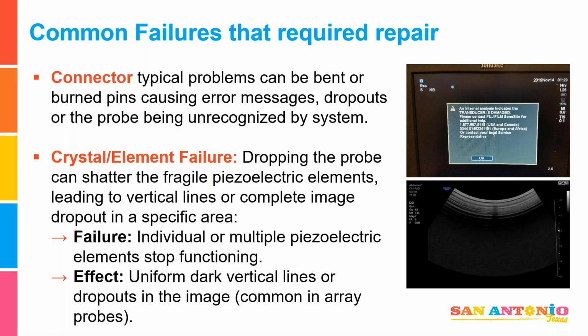In this case, I'd try multiple probes in multiple ports, making sure my pins aren't bent if I'm going to move them around. You want to figure out if it's a probe problem or a system problem first, and the easiest way is to put the probe in a different port. If it moves with the probe, try a different probe in the same port. If the problem goes away, then it's a probe problem. If it doesn't, and it's on multiple probes, then you have a system problem, and you can start working on it.